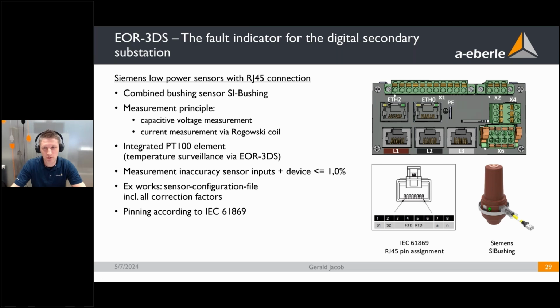And compared with the competitors, there's also one feature I really want to emphasize here. The sensors come ex works with a so-called sensor configuration file, including all correction factors. Normally each sensor has an amplitude correction factor and a phase correction value that you have to set in each device per sensor. So 3 times voltage, 3 times current measurement. For each of these 6 measurements, you have 1 amplitude correction factor and 1 phase correction.